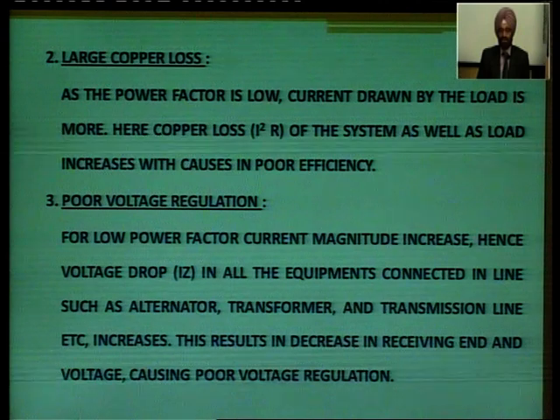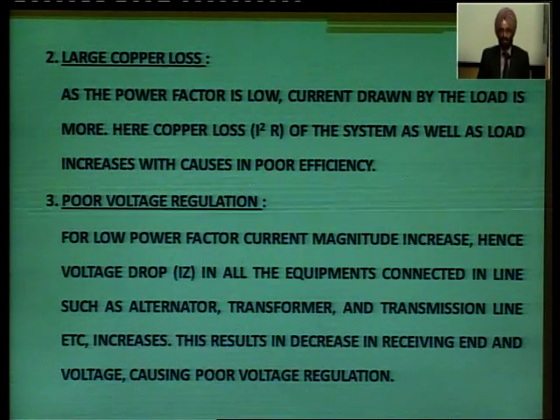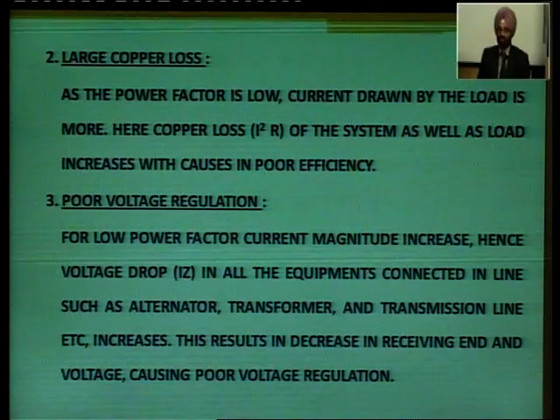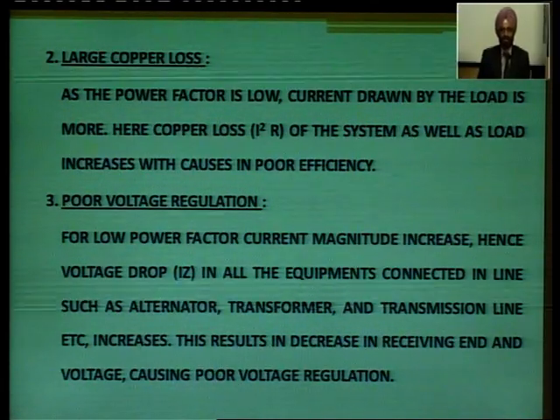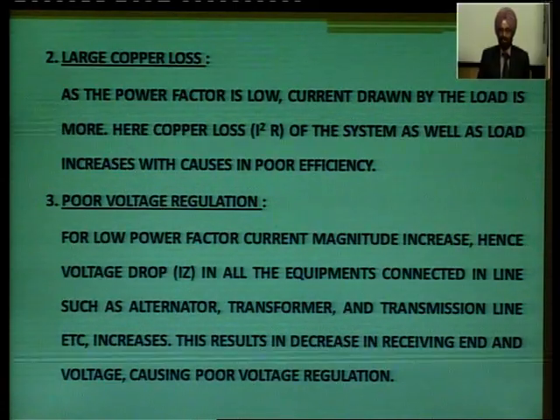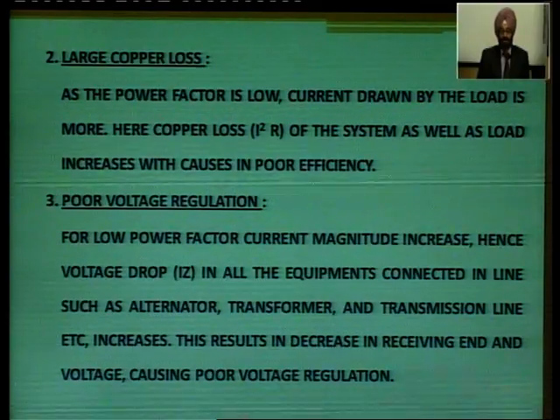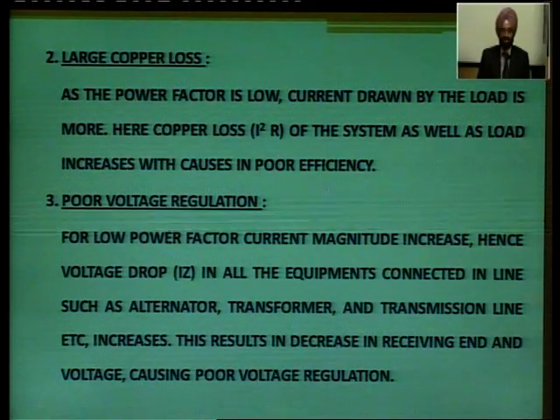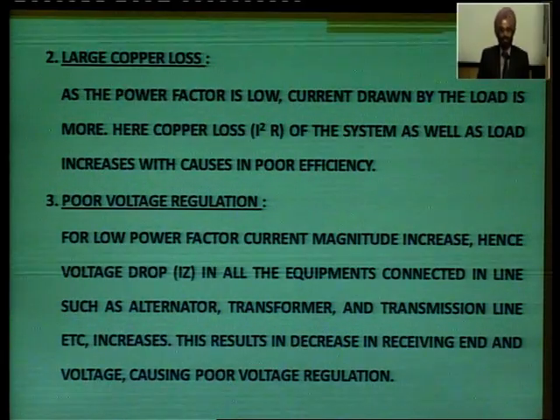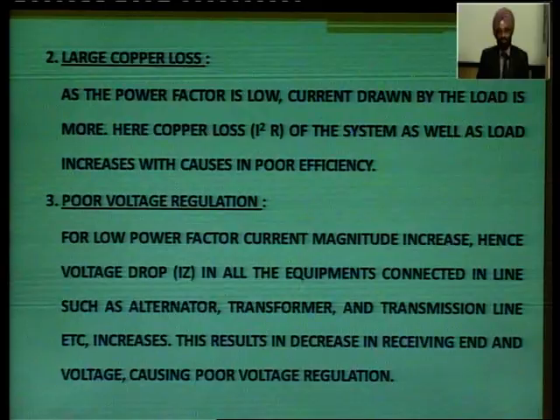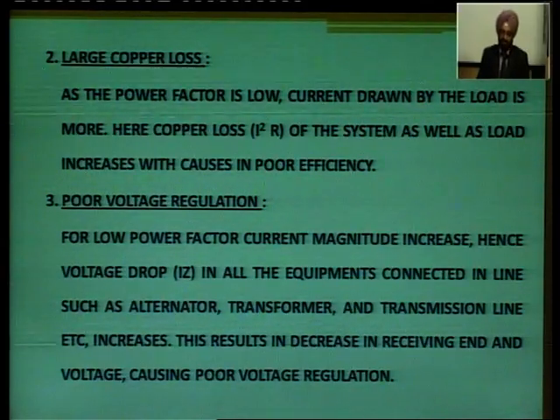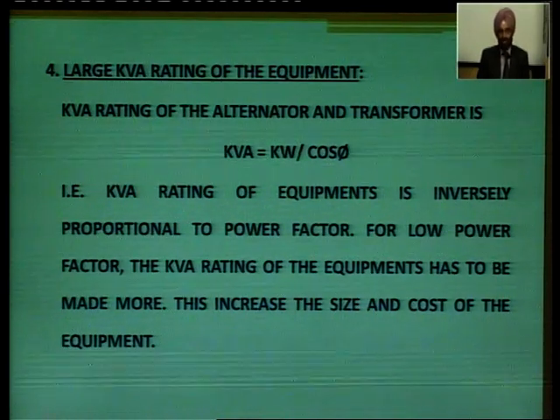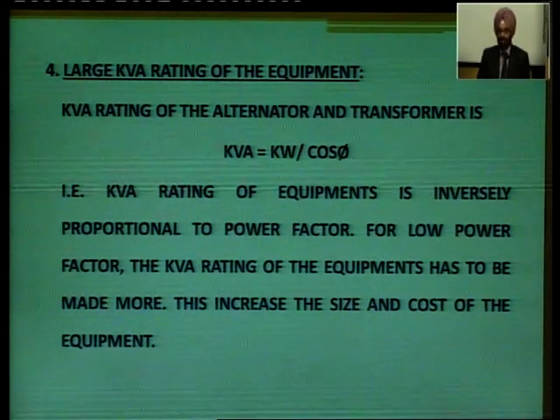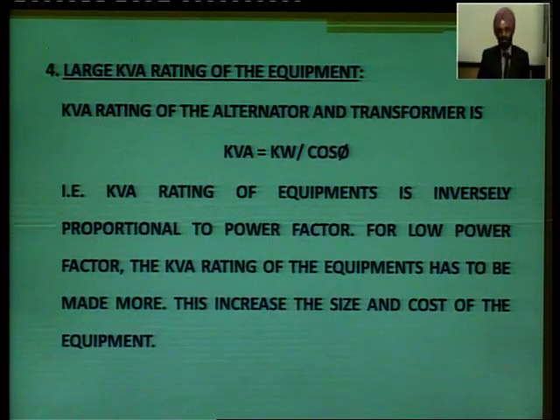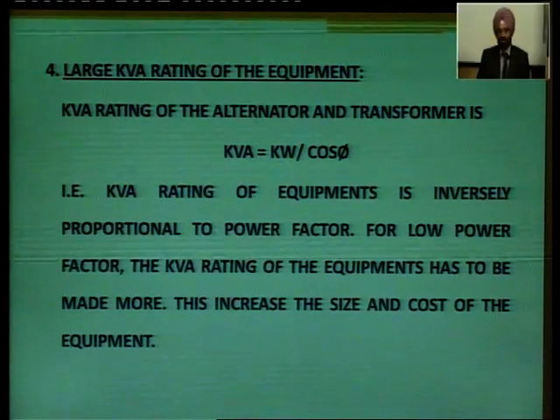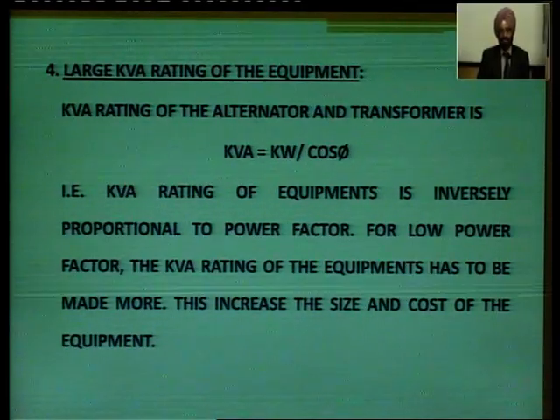Then we have poor voltage regulation. For a lower or lagging power factor, the current magnitude increases, hence the voltage drop in all the equipment connected in the lines, such as alternators, transformers and transmission lines, increases. At the receiving end, the difference between the sending end voltage and the receiving end voltage becomes more and more, and we have poor voltage regulation. And the last is the larger kVA rating of the equipment for the same load.